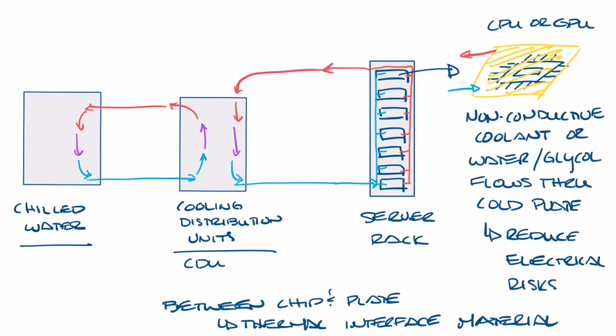The warm liquid that leaves the chip travels back to the CDU, where the heat exchanger transfers the heat and it goes back into the chilled water loop or cooling tower so it can be rejected outside the data center. Let's move this over again.